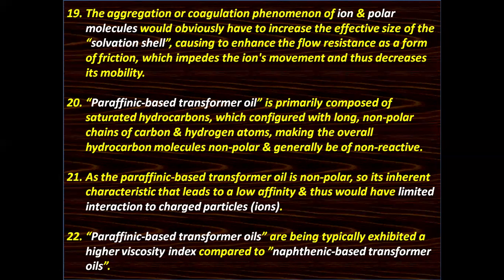Paraffinic based transformer oil is primarily composed of saturated hydrocarbons configured with long nonpolar chains of carbon and hydrogen atoms, making the overall hydrocarbon molecules nonpolar and generally non-reactive. As the paraffinic based transformer oil is nonpolar, its inherent characteristics lead to a low affinity and thus limited interaction with charged particles.